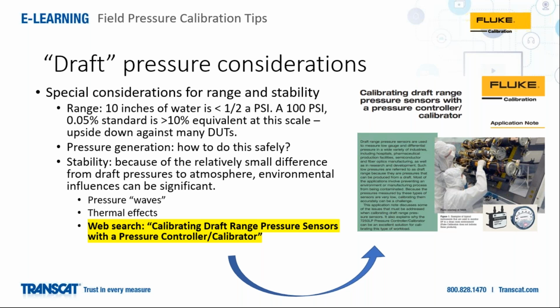There are some things that can be done to help that. Adding more volume to the external system can give you more control resolution, possibly at the expense of some other factors like stability.